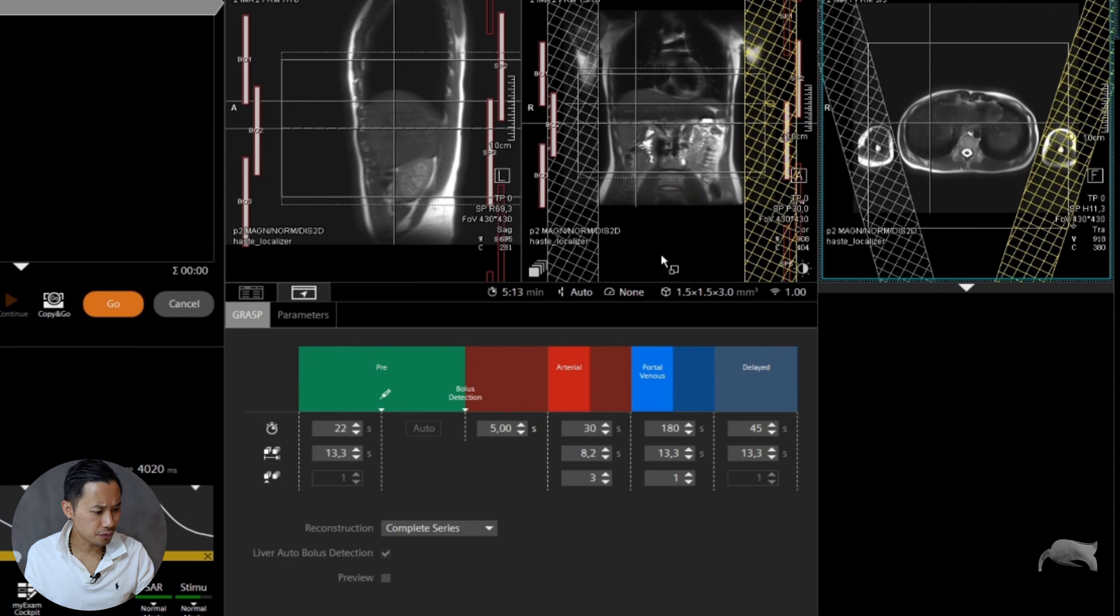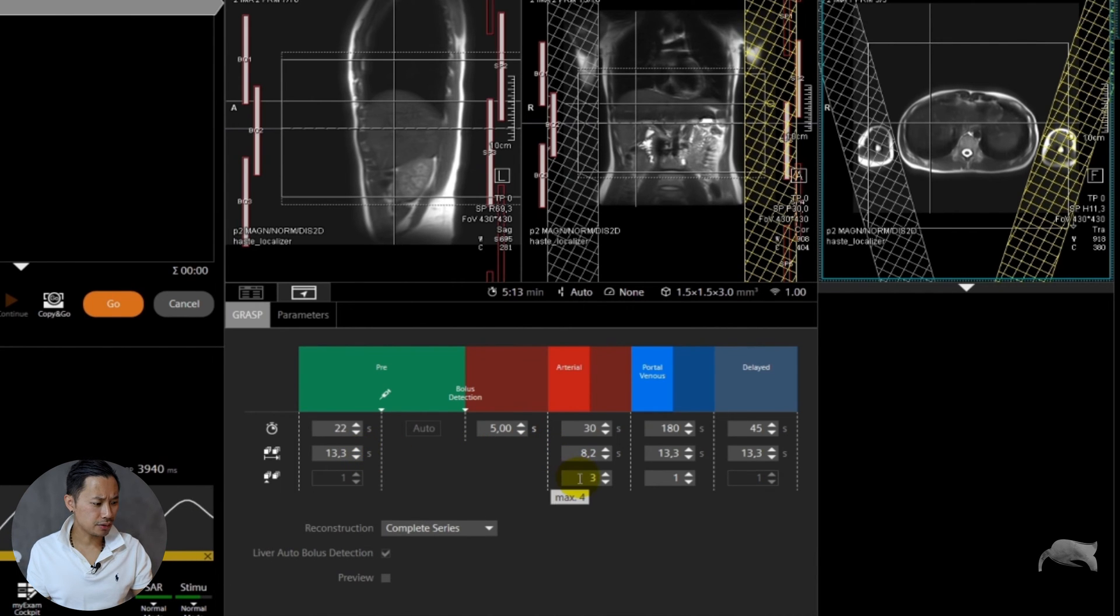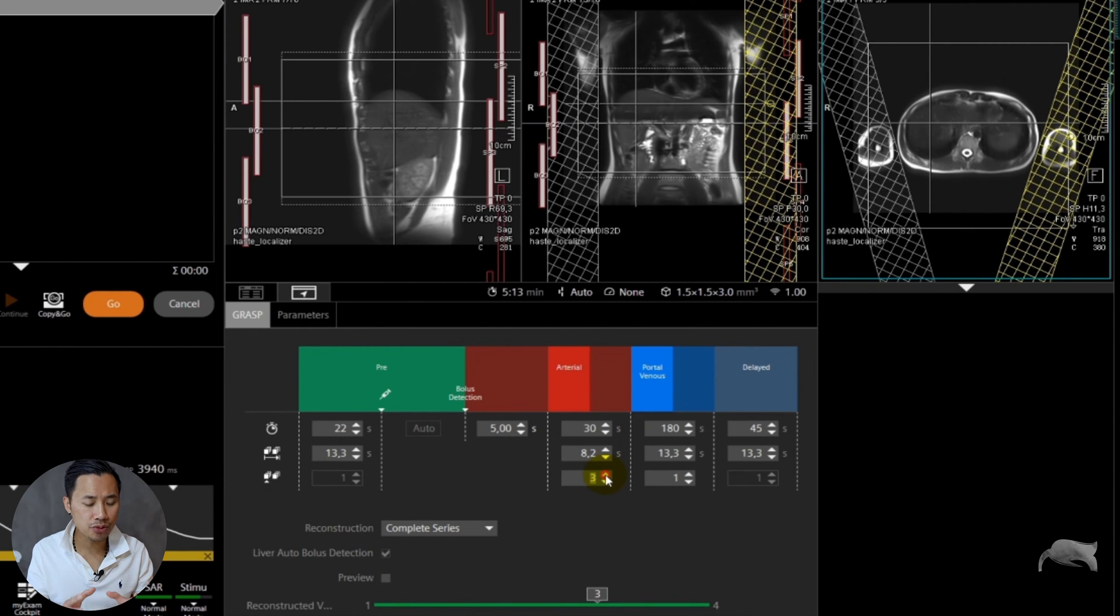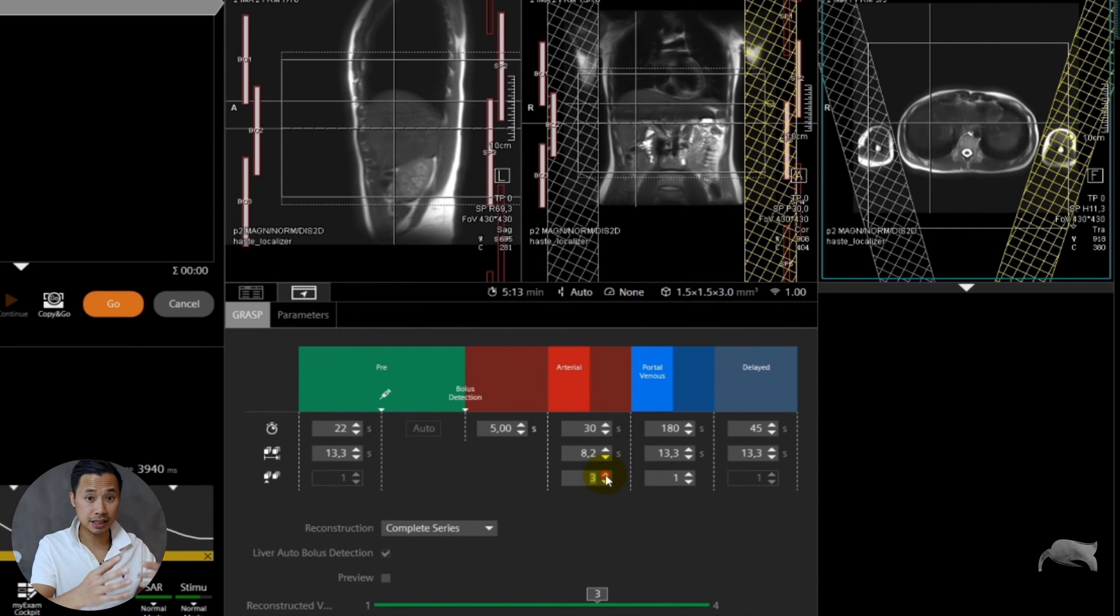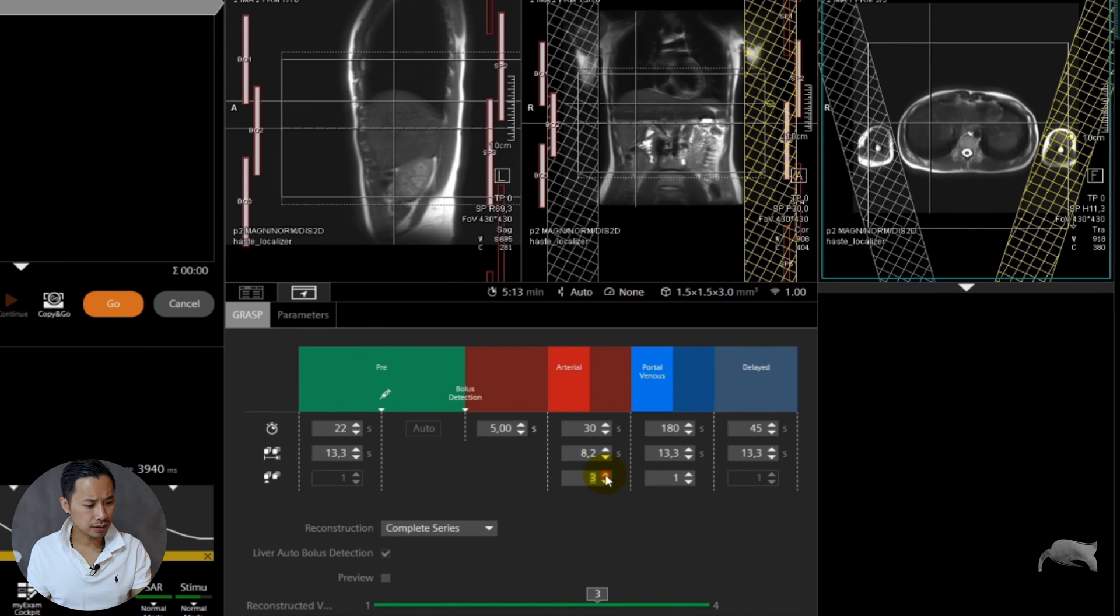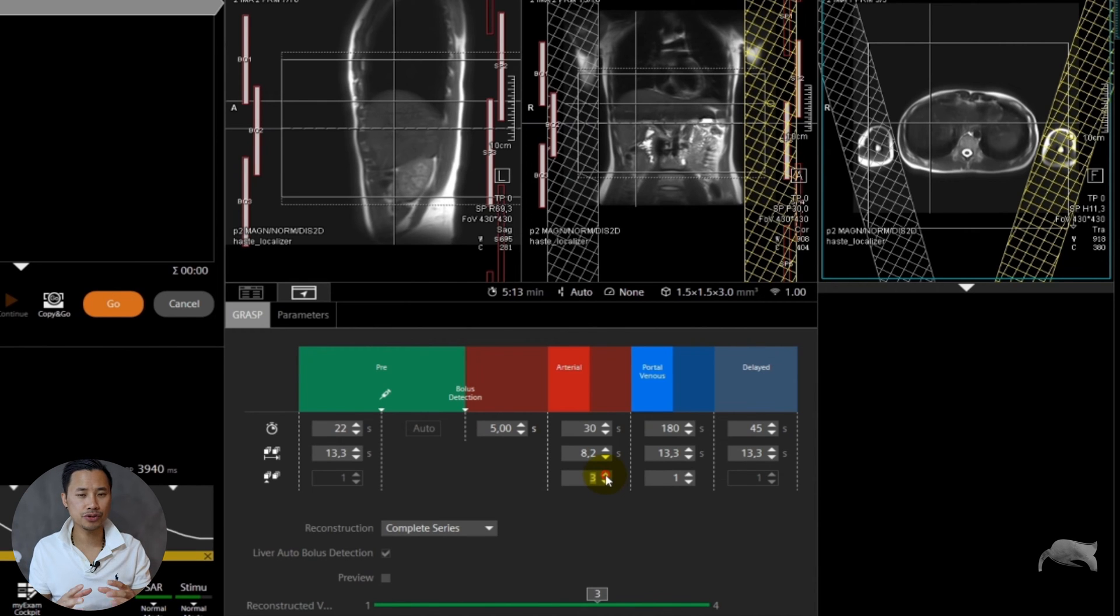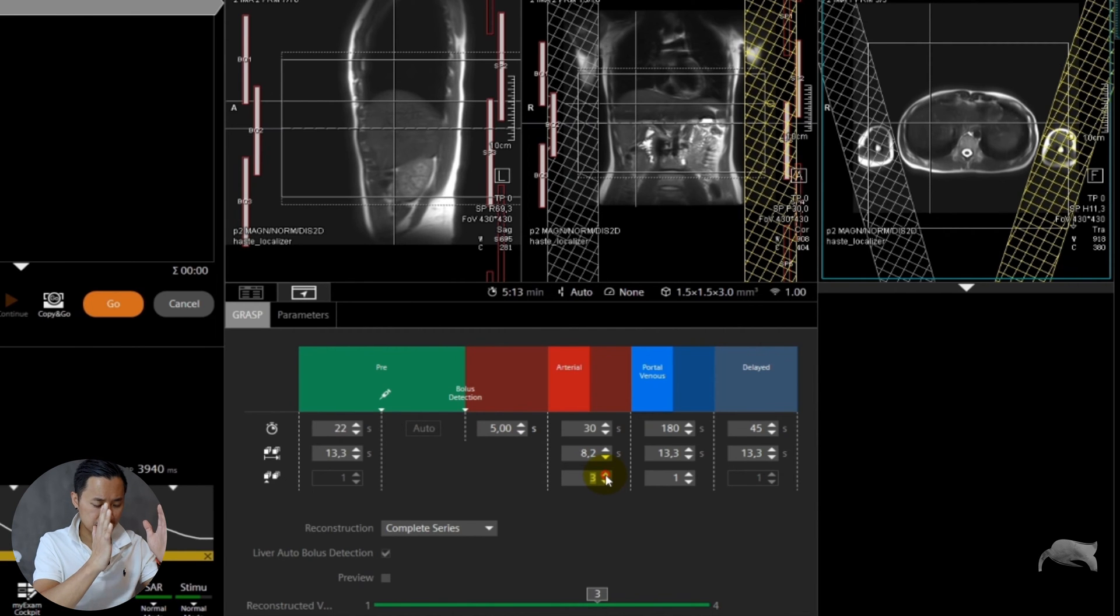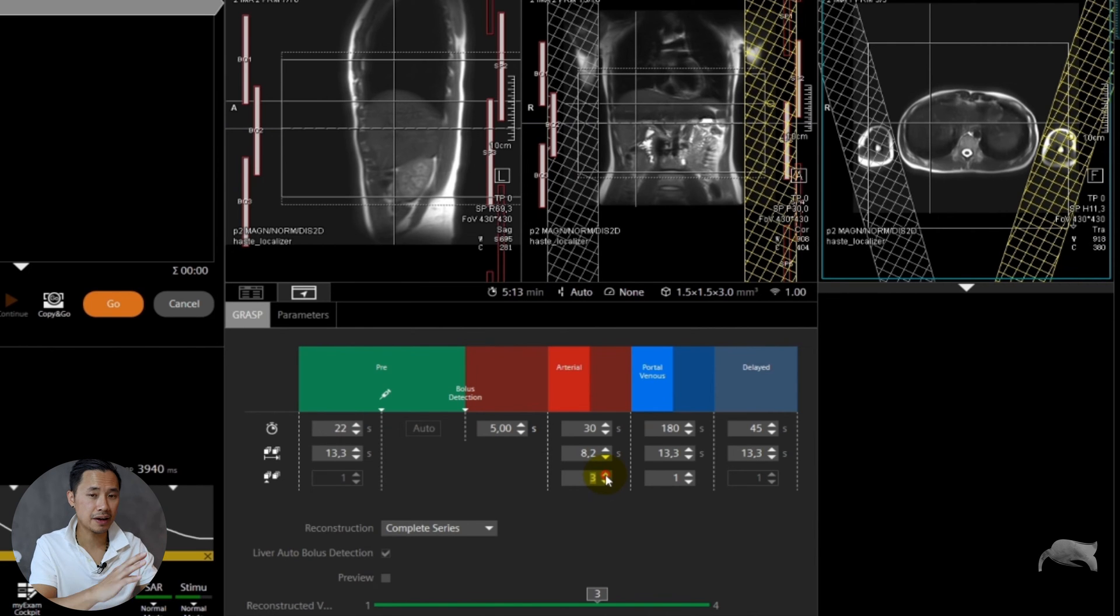I'm gonna go through with you this preset and explain how it works. As you can see here in arterial phase, you have multiple arterial phases. You can see three arterial phases but there's room for four. This depends on how you set up the field of view, the matrix and slice thickness, how many slices you have and so on. Siemens here already has three multi arterial phases with a temporal resolution of 8.2. Temporal resolution is the time between one sequence to the next sequence.